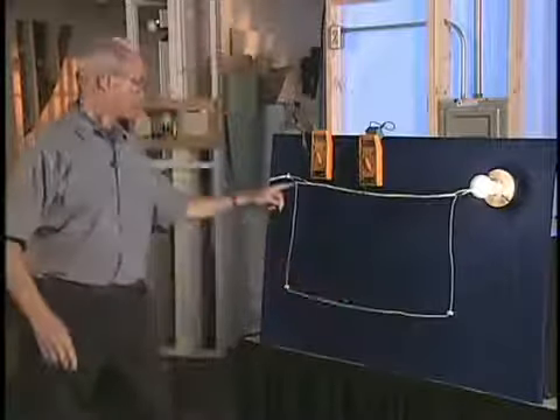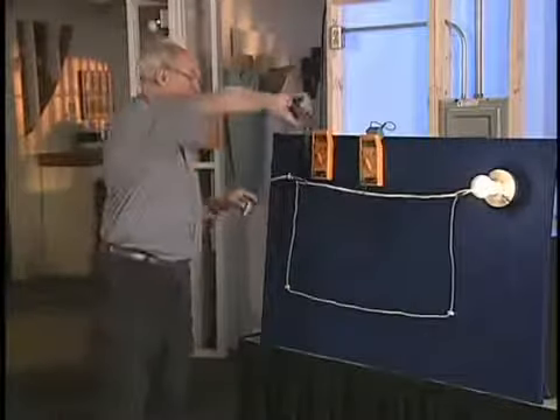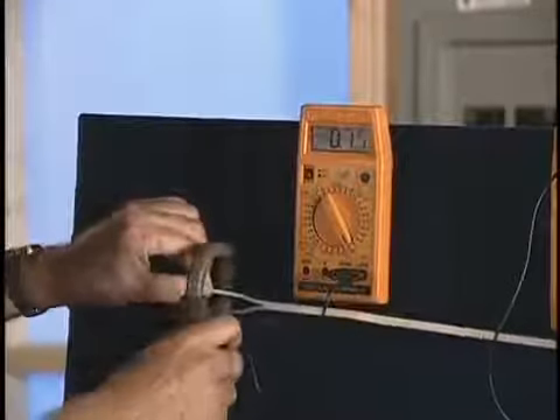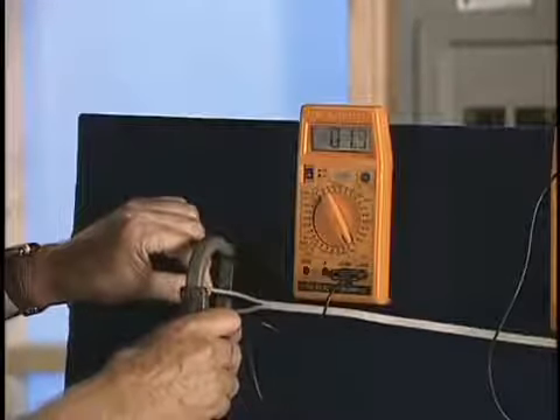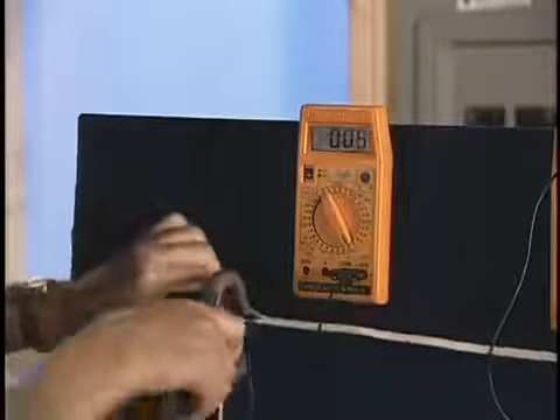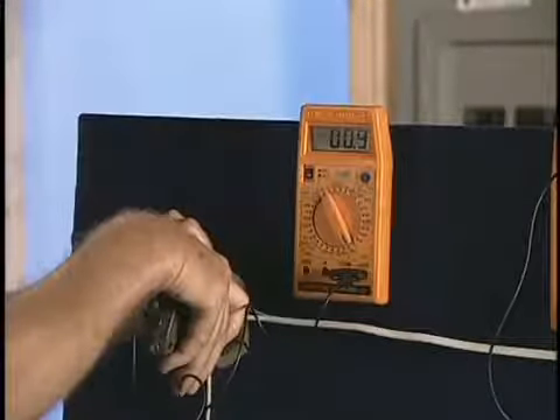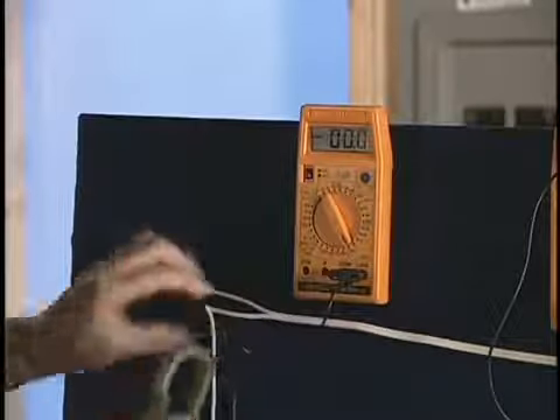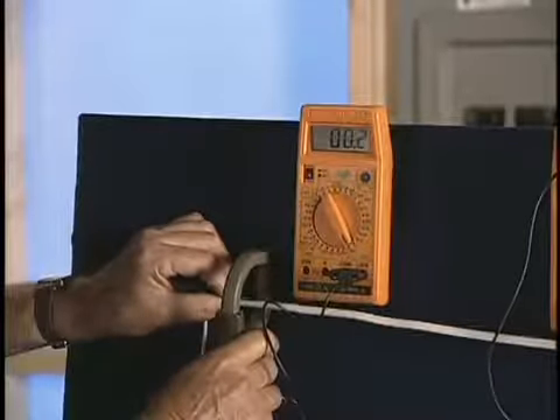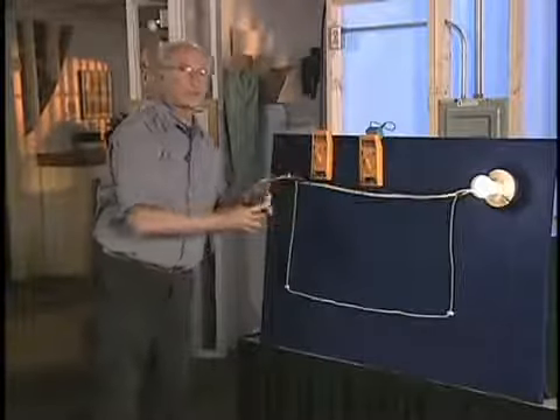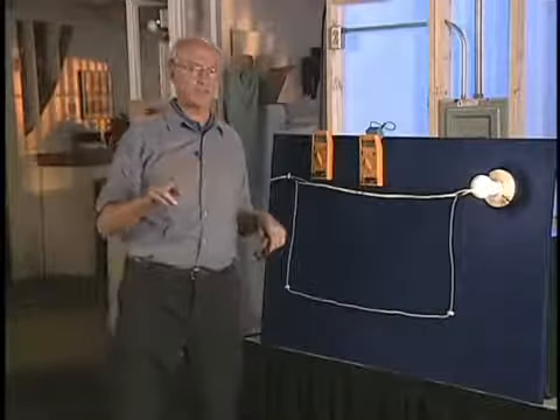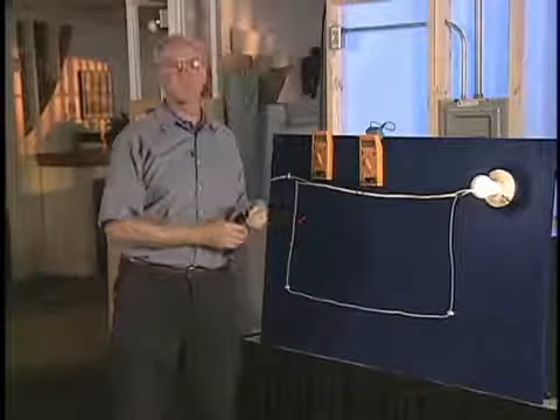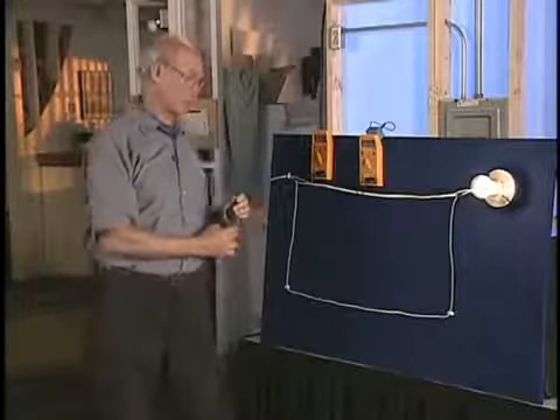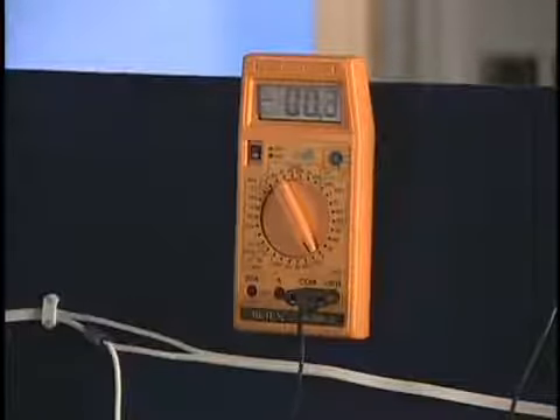Now let's see if our measurements verify the theory. We've added a parallel neutral, but kept the load the same. The hot still measures 1.2 amps. The dedicated neutral now measures 0.9 amps. Clamping around both, the net current is 0.3 amps. We see that the net current is the remainder of the neutral subtracted from the hot. We would now expect to see the missing 0.3 of an amp on the parallel neutral. We measure 0.3 of an amp.